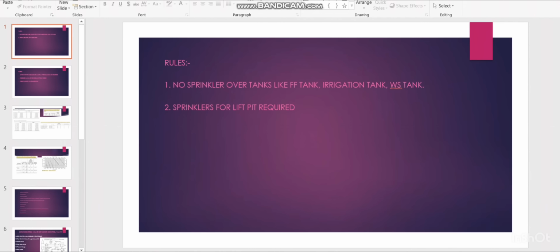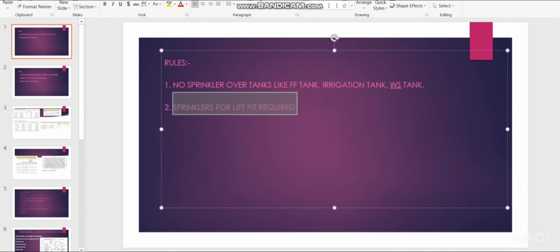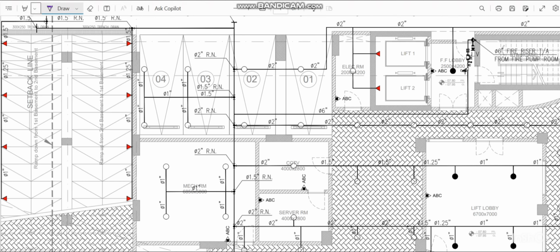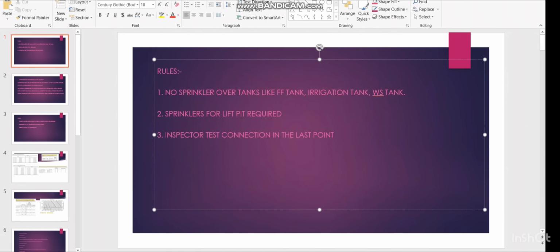And the next important rule is that a sprinkler for the lift pit is required as per NFPA 13. So this is the lift. We have provided 2 sidewall sprinklers. The rule is, normally if you see the section, from the bottom 600 mm maximum, within the 600 mm you have to provide one sidewall sprinkler. The pipe will be taken like this, it will go down, and you provide the sidewall sprinkler. So I have provided the sidewall sprinkler for the lift pit.